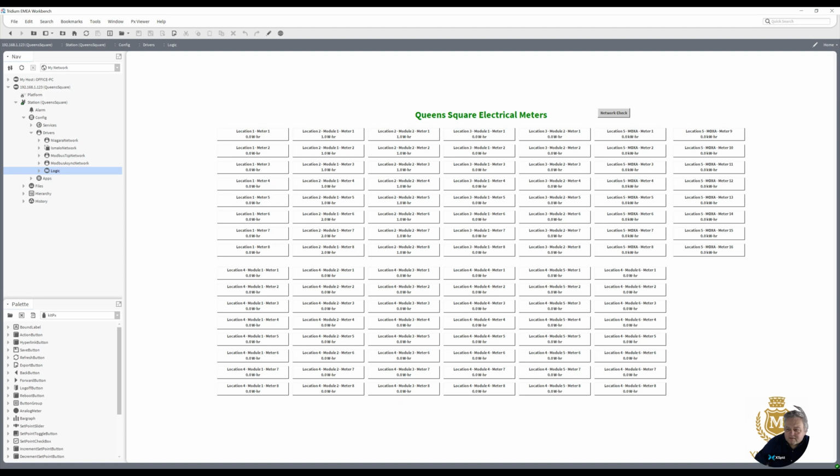I showed you how to design a meter system with the pulse meters going into a MAC36NL controller, and also connecting an ISMA 8i IP module into the system, and then connecting to that an ISMA 8i RS485 Modbus module. So I didn't go all the way through it all. I showed you each aspect of installing, commissioning a station, installing it all.